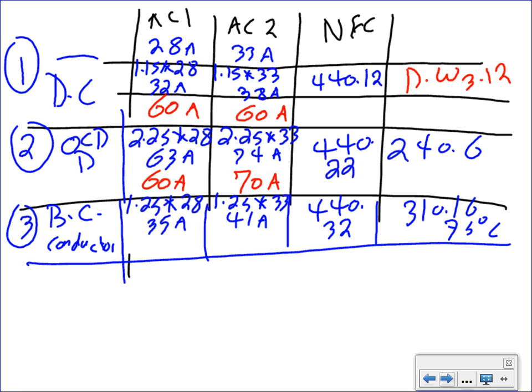What's the 35? Can I get away with number 10? Under 75. Don't forget the 75. Number 10? 10. How about 41? Can I get away with number 10 or do I have to go to 8? Have to go to 8. Number 32. Can I get away with 12 or do I have to do 10? No, sorry, never mind. I thought this is 32. What do you have to do for the 75?